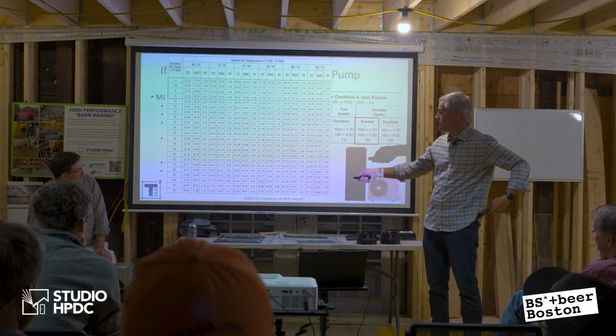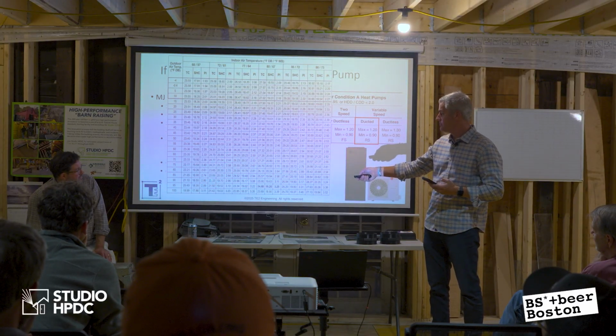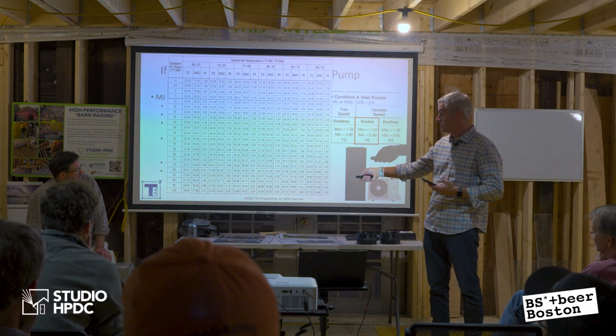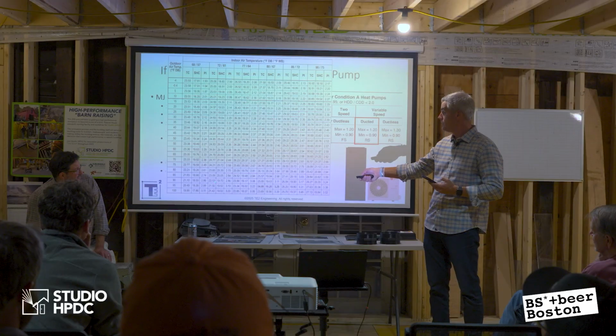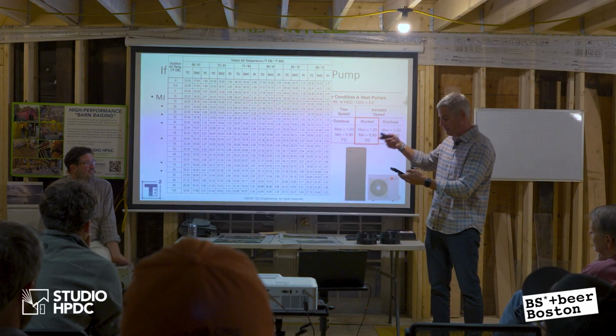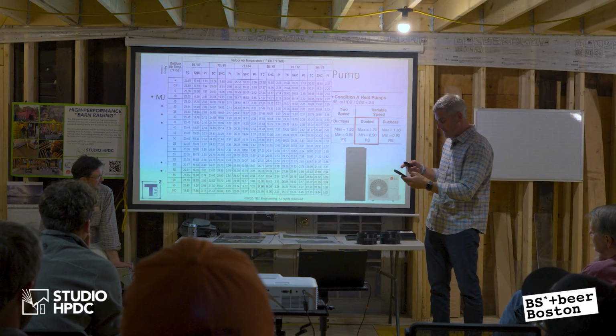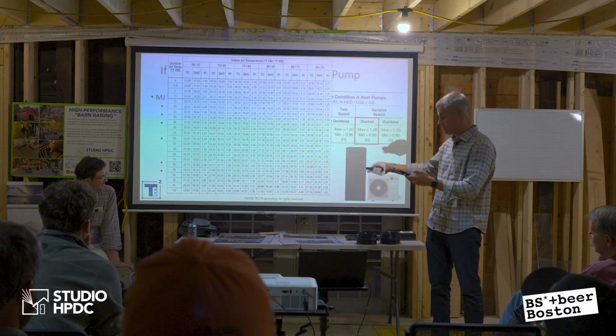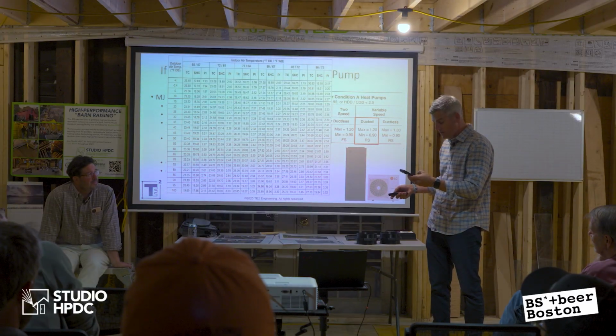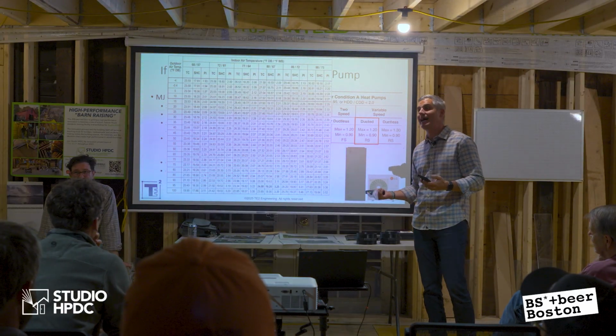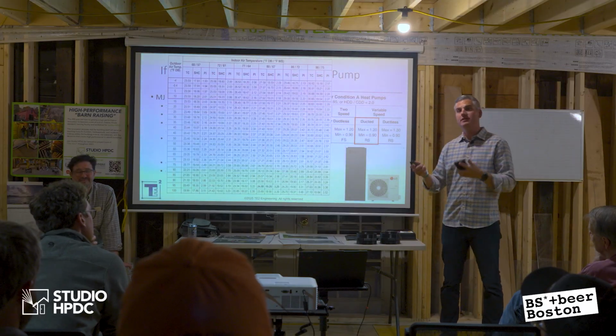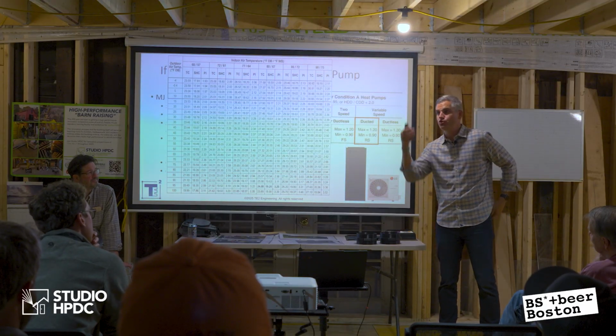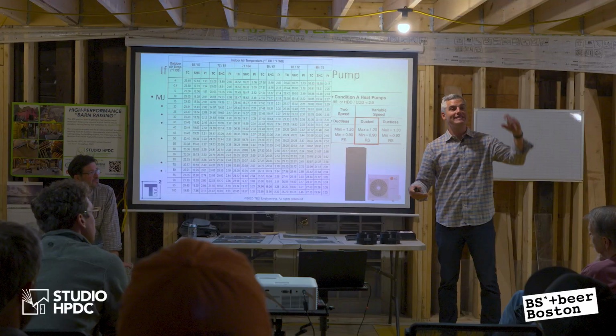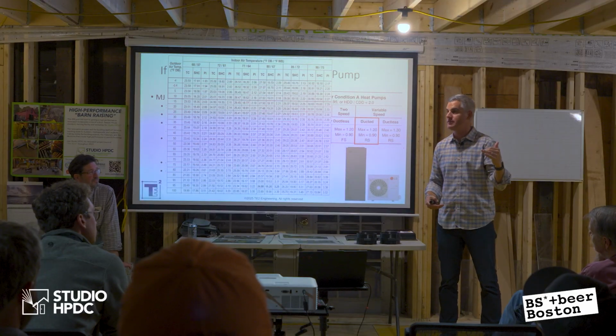So if I look at this unit, it's going to give me 22,000 BTUs of cooling total, but it's going to give me 19.7 thousand BTUs of sensible. So the sensible heat ratio, if I do the ratio of the 19.7 into 22.5, it's 89%, so it's 90%. So meaning that if I run this system, 90% of it drops the temperature of the room, 10% of it drops the moisture in the space, right?